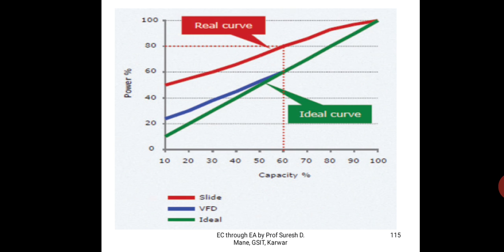Now please understand, you see this graph, all along I am telling you that you should go for full loading, not part loading. At 100% loading on the X-axis, the power requirement is 100 percent. Now you see here, this real curve is for 60% loading, the power consumed is 80%. So that is high. Just imagine, 60% loading should mean 60% power, but it is not the case.